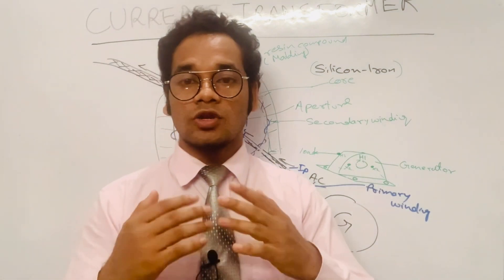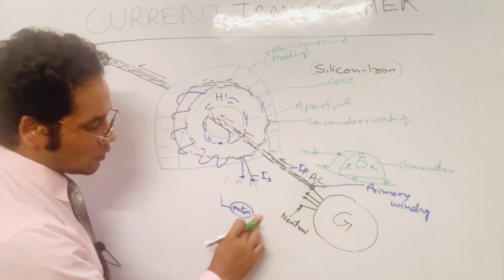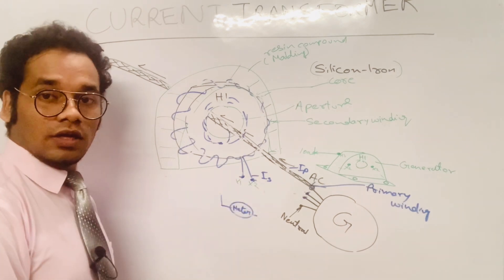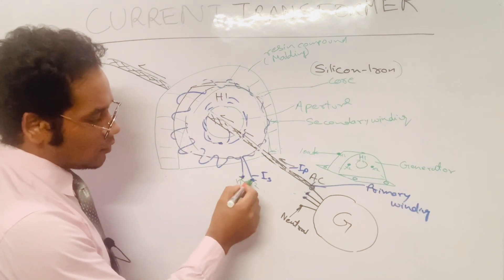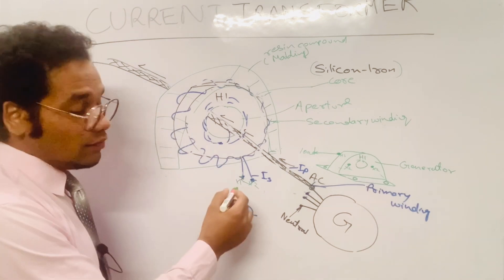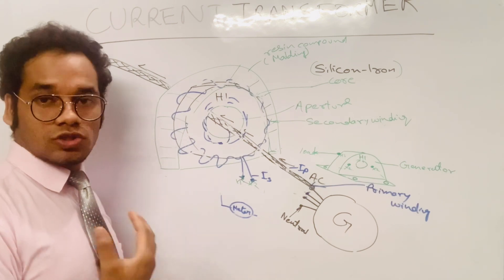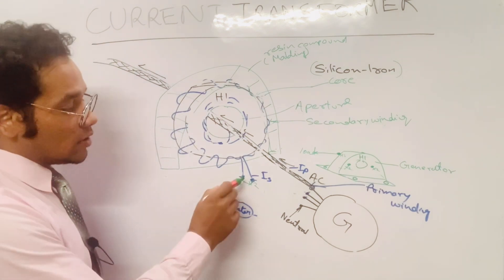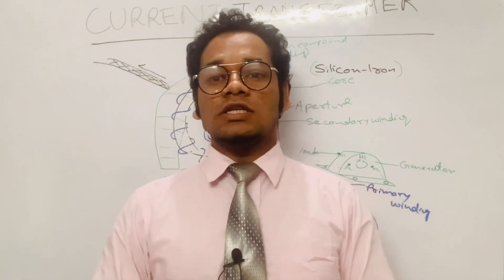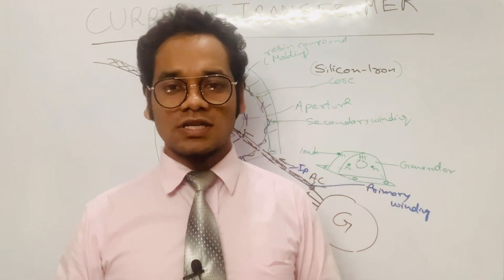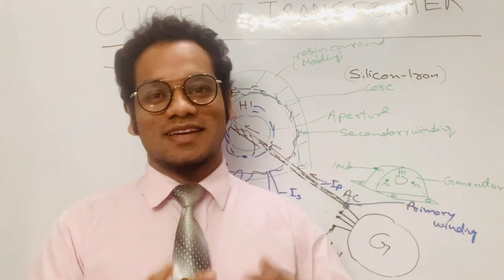One important safety point: suppose the current transformer has been disconnected from its circuit. Make sure that the two terminals X1 and X2 are shorted together — joined by a conductor. If you don't connect both terminals and anyone touches them, they can get a severe electrical shock, which is very dangerous. So the terminals of the current transformer must be connected together whenever it is removed from the circuit.